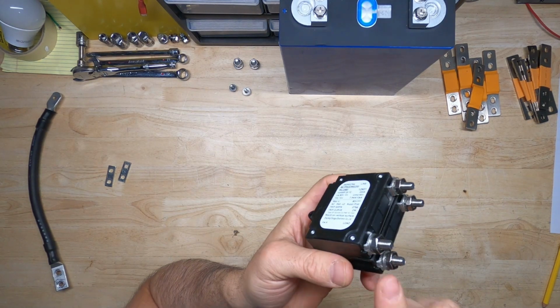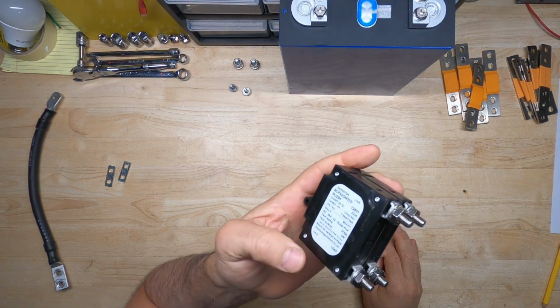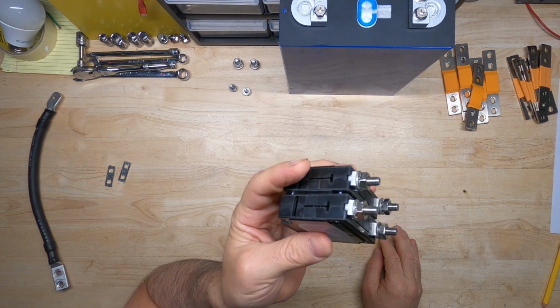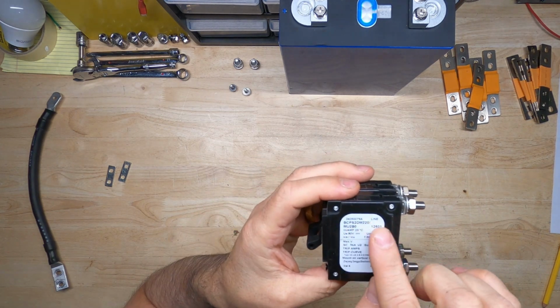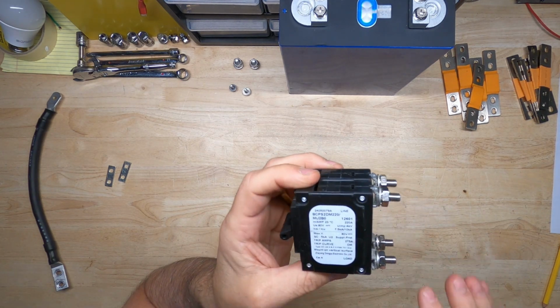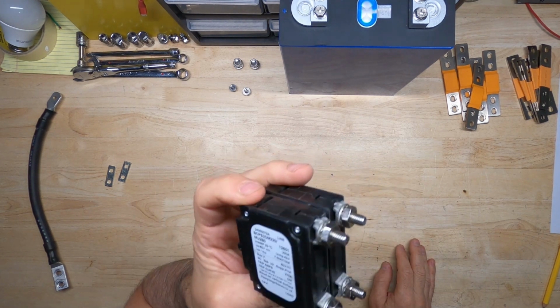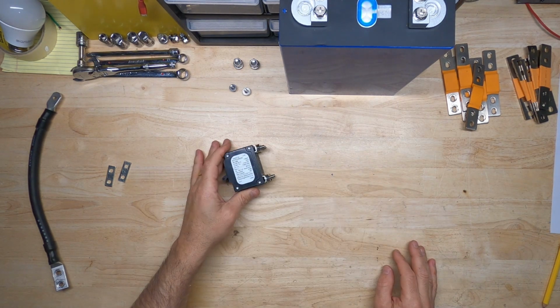I think the contact terminals are just too small on this for 200 amps, and that's what's creating most of the heat. And internally we saw a lot of heat being generated inside the breaker itself. So I think this is insufficient. I give this a fail.